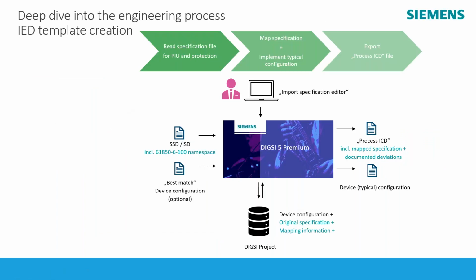So the workflow I will show is how to read the specification file for both devices, the protection device as well as the merging unit, to map it to the signals provided by default by the manufacturer product, and how to deliver the process ICD file. The process ICD file will have the particularity of including the specific mapping as well as the deviations, if any are found in the product, where some logical nodes or some names cannot be realized in the vendor tool.